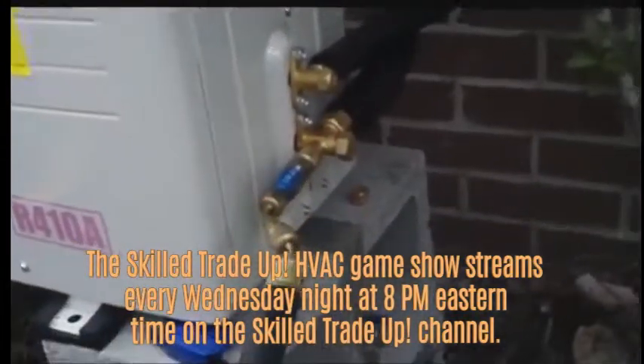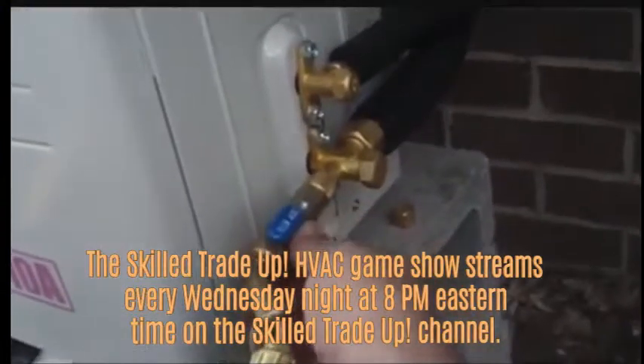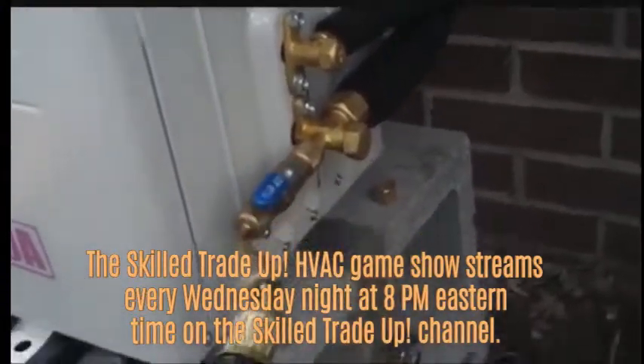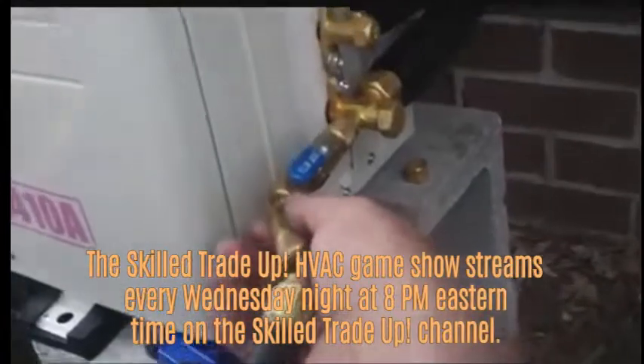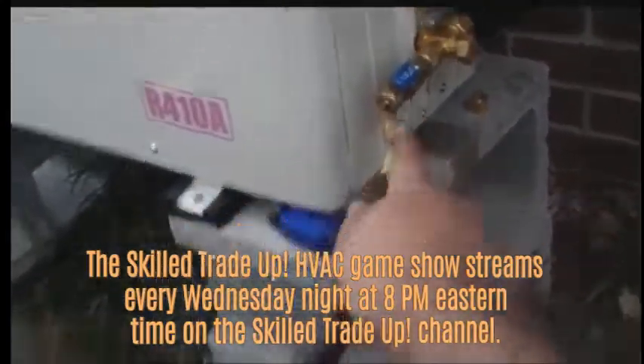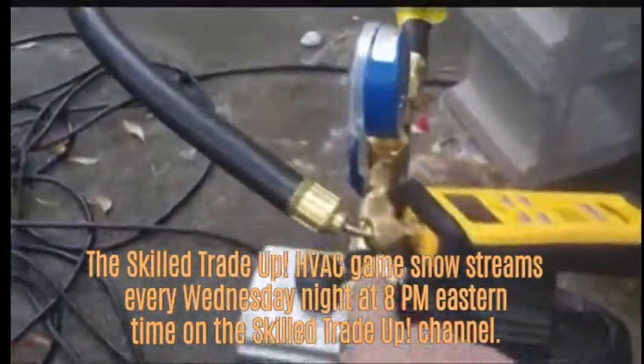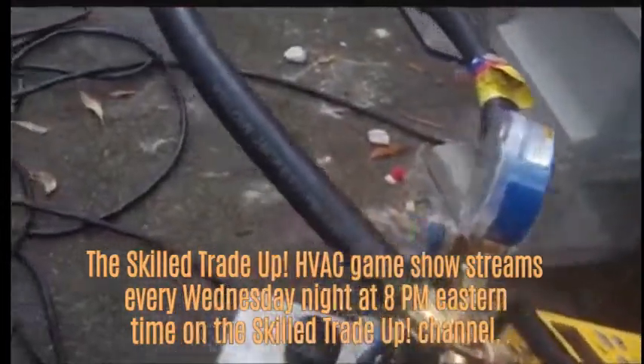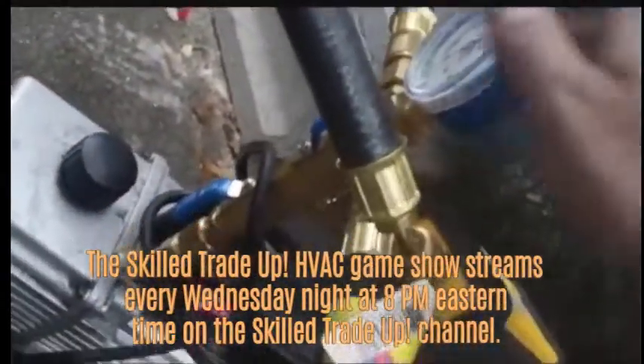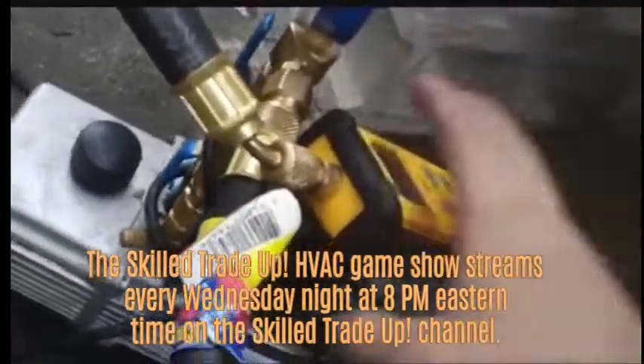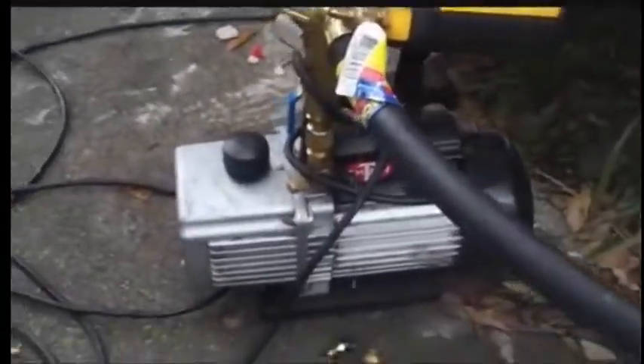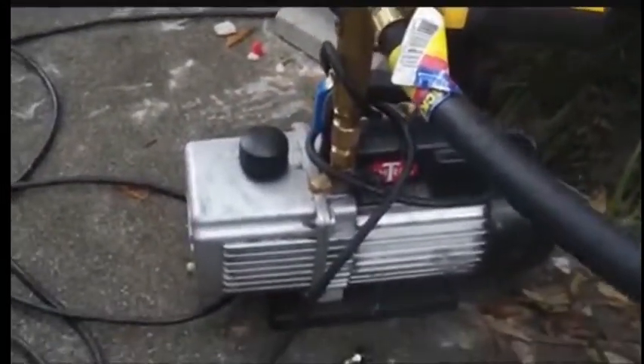Alright, I'm pulling a vacuum now. I have the 5/16 core remover on the mini split so I can remove the core, which makes the vacuum move faster. I have the adapter down to 1/4 inch and a 1/4 inch head on my 1/2 inch hose, which goes back to one of two hoses that go to my vacuum manifold from Yellow Jacket. I have the vacuum gauge hooked up to one. As you can see, we're pulling down nicely. It's only been running about 3 minutes, but this sucker does a real good job. It's just a generic pump, the same one I had when I started my business. One day I'll get a better one, but it still does the job real good, so what can you say?